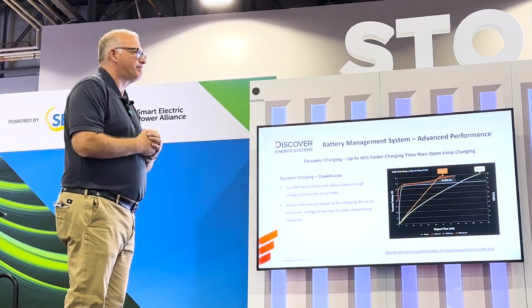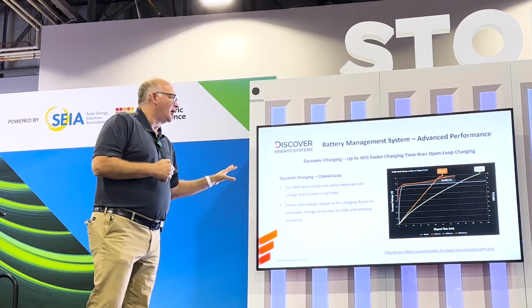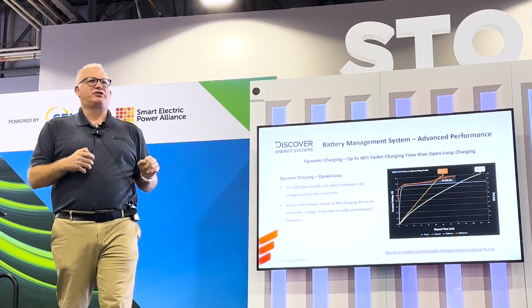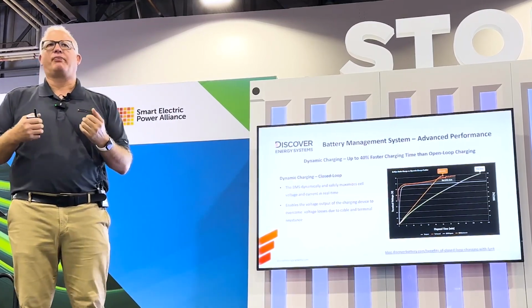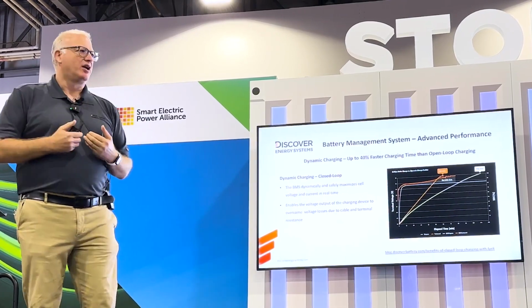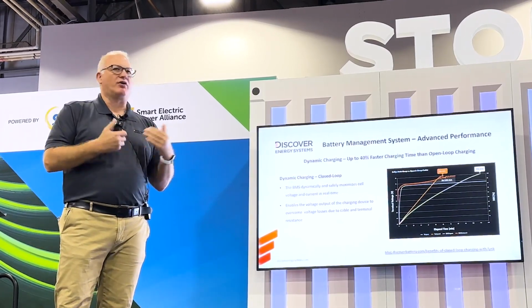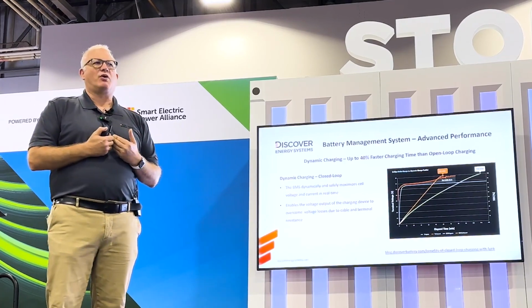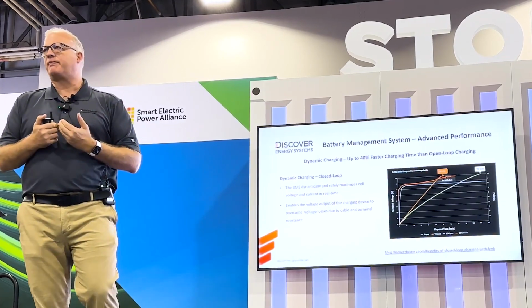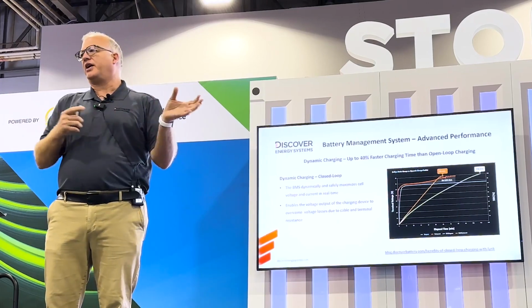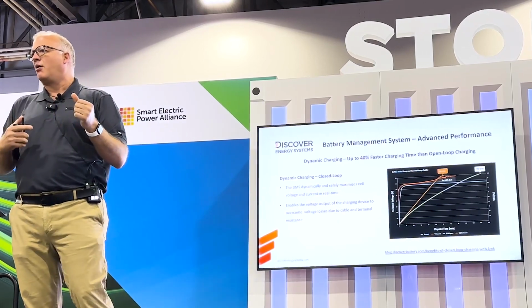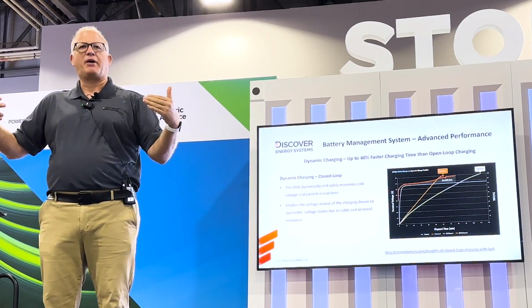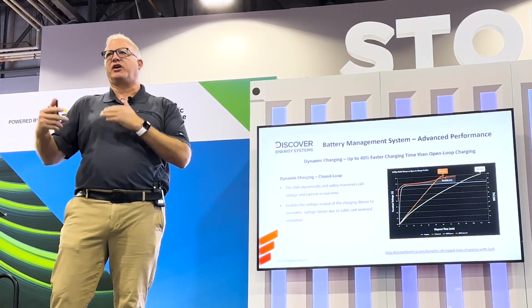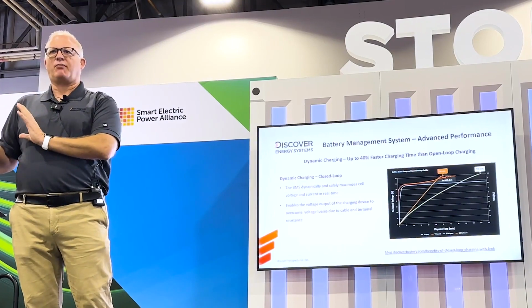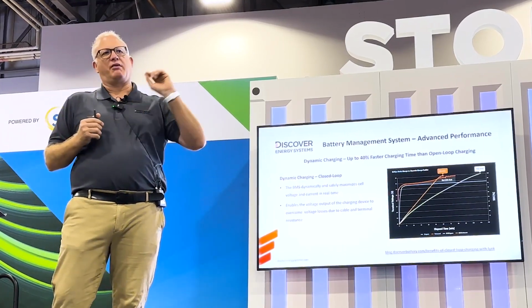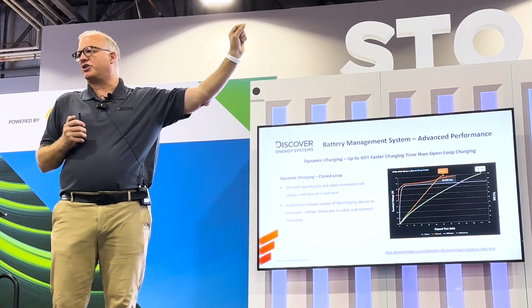I'm going to talk about some of the advanced aspects of that. At Discover, we call this dynamic charging or dynamic performance. With our batteries, we communicate and take all the voltages of the various modules connected together in parallel, look at the cells, do averaging and some math, and come up with a number. We then send that to the inverter as a target.